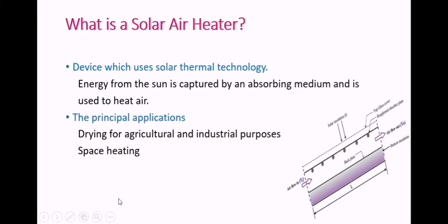The solar air heater can be constructed with face areas ranging from 1 to 2 meter square. Materials of construction and sizes are similar to those used with liquid flat plate collectors. Thus, the absorber plate is a metal sheet about 1 millimeter in thickness, usually made of galvanized iron or steel.